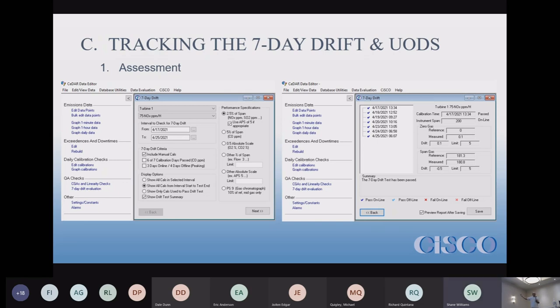With the, I think that's blue. I'm colorblind, so I'm assuming those are blue check marks. With the blue check mark, you see 7 unit operating days for the 7 day drift test. And it seemed like the test had passed successfully. But one of the shortcomings is that the 7 day drift checker only checks days when you've done a calibration. At this point it doesn't check whether the unit operated without a calibration. And for the 7 day drift test, you have to run a cal every day you operate.